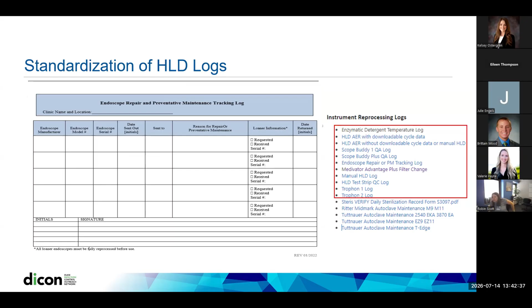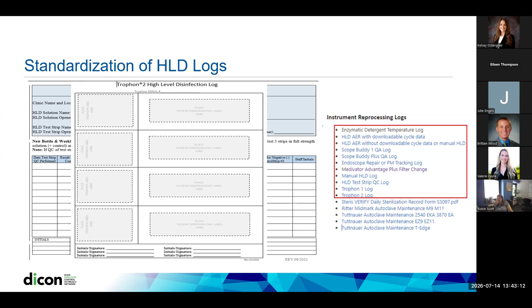If they had a flush device, we used this log. If they had endoscopes that needed to be logged for repair and preventive maintenance tracking. Again, if they had an AER, they needed to keep track of their water filter changes and their water line disinfection. We also have manual high-level disinfection going on, as you saw in those pictures. Some of our ENT clinics and ophthalmology clinics will use these logs. And then we also have Trophons, both the current model and the older model, so there are a couple of different Trophon models. We work really closely with clinic leadership to say, okay, here's what you have and here's what you're reprocessing.